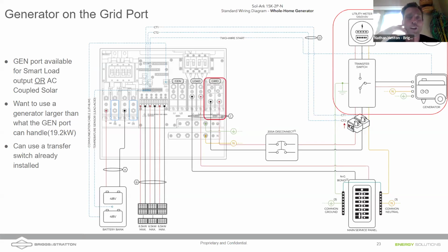The moral of the story here is that the Solark, unlike some other inverters, is smart enough not to backfeed the generator, but still allow you, once that transfer switch goes back to grid, to backfeed the grid with your excess solar. So that's a great feature. Yeah, and I've heard John Cromer give caution to this. If you have a very large generator, that may cause some complications, because then the Solark isn't going to necessarily recognize that.